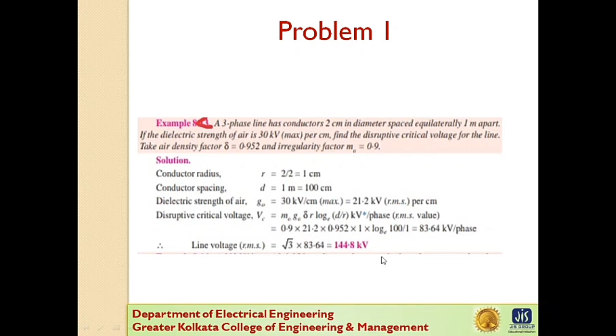So what is the line voltage? Line voltage is equal to root 3 into phase voltage, that is 144.8 kV. Next problem: a 3-phase 220 kilovolt 50 Hz transmission line consists of conductors of 1.5 cm radius, spaced 2 meters apart in equilateral triangular formation. If the temperature is 40 degrees centigrade and atmospheric pressure is 76 centimeter, calculate the corona loss per kilometer of the line. Take the value of M0 as 0.85.